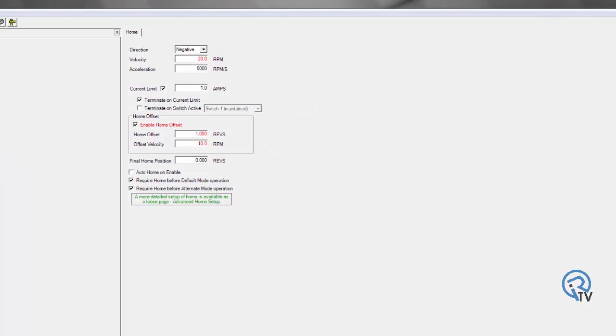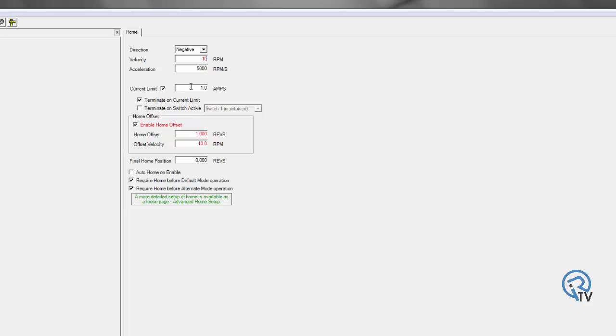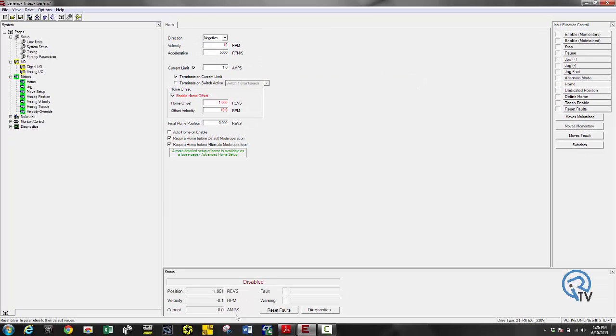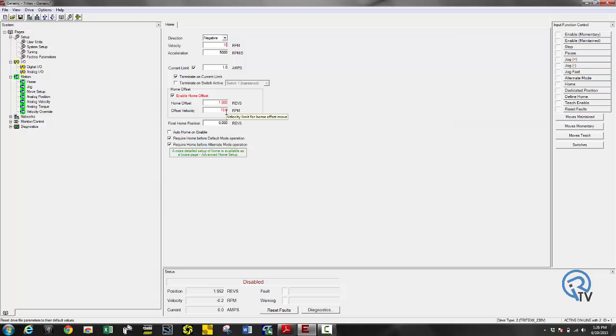First thing we'll look at is my home. Here's where I can specify what direction the drive is going to operate at what velocity and acceleration. I'm going to want this home out at 10 RPM. And it's also going to stop at a current limit. So when this thing retracts back to its hard stop position, I'm going to specify a current limit at 1 amp. So when I hit 1 amp of drive power, it's going to terminate on that position. And I can also say I want this to, once I hit my home current limit, it's going to extend back out at 1 rev and 10 RPM.